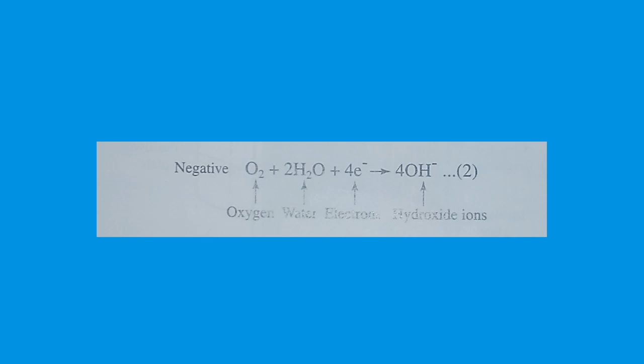One type of nickel cadmium cell uses positive and negative plates, a separator, alkaline electrolyte, a metal case, and a sealing plate with self-resealing safety vent. It is shown in figure 5-12. The positive plate of this battery is a porous powdered nickel base plate. It is filled with nickel hydroxide. The negative plate is a punched plate of thin steel coated with cadmium active material. The separator is made of polyamide fiber for high temperature uses. It is made of a non-woven polypropylene fiber. The positive plate, separator and negative plate are pressed together, wound into a coil, and inserted in the metal case. The electrolyte is an alkaline aqueous solution. It is totally absorbed into the plate and the separator.